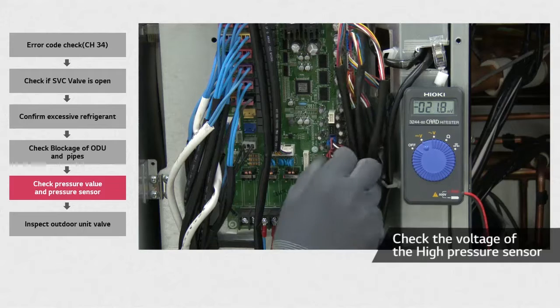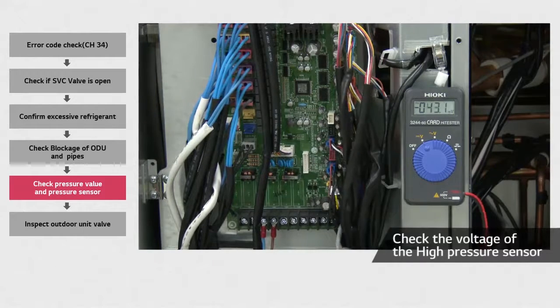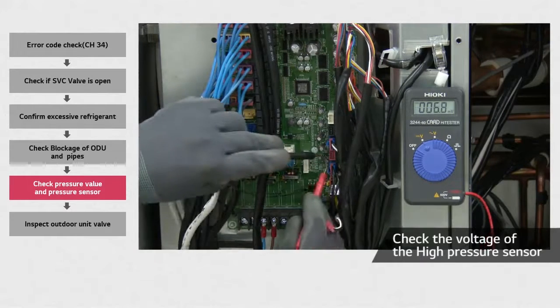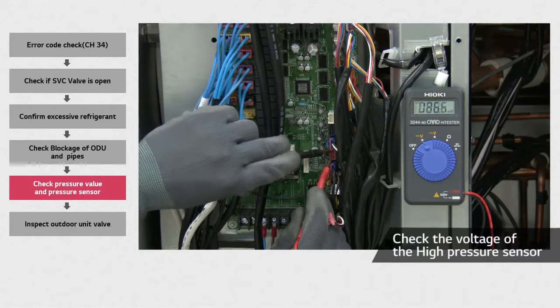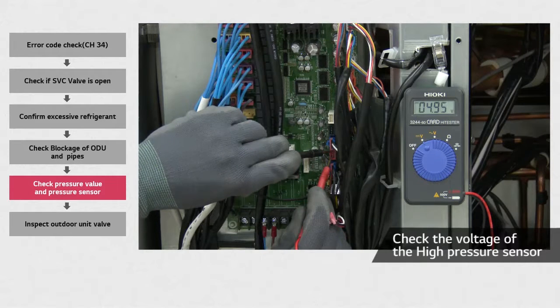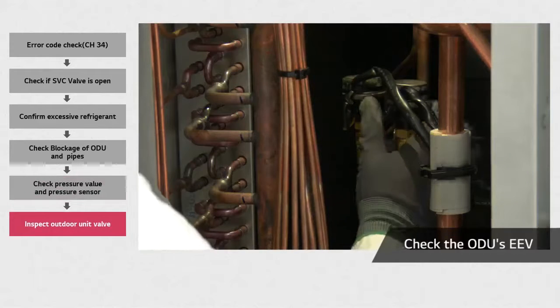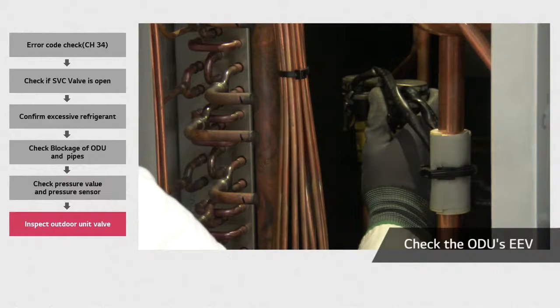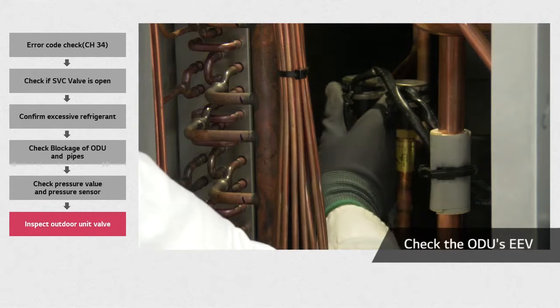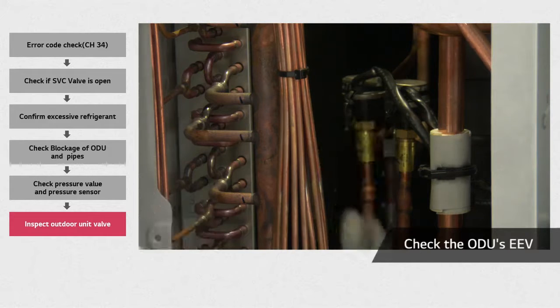Check the voltage of the pressure sensor on the external PCB. The DC voltage measurement should be from 0 to 5 volts on the red high pressure connector. Next, check the electronic expansion valve. When you reset the ODU power, the EEV opens and closes again, and when you hold the valve in your hand, it should be vibrating.